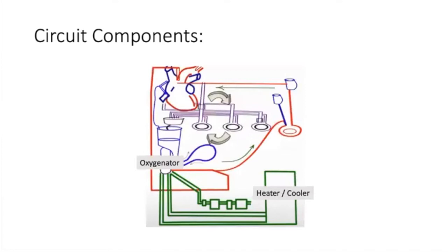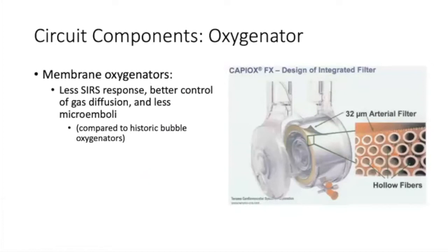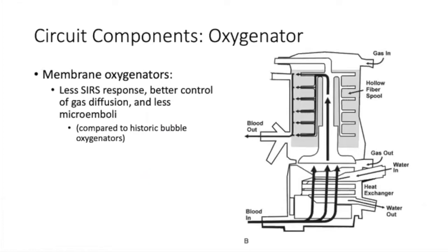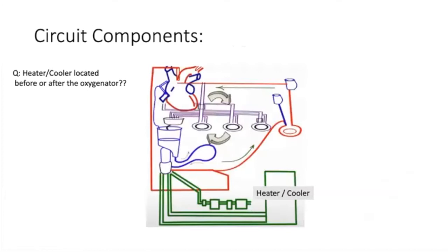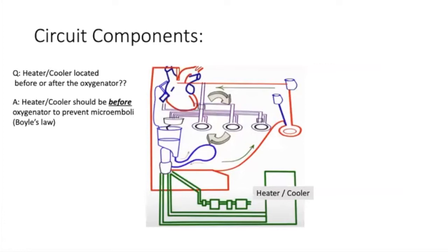Membrane oxygenators are essentially the only oxygenators in use today. They offer much less SIRS response, better diffusion control of gases, and less microemboli compared to historic bubble oxygenators. The heater-cooler uses a heated coil with a water bath to adjust blood temperature as it flows through. A common source of confusion is whether the heater-cooler should be before or after the oxygenator — it should be before, to prevent microemboli and outgassing: if blood already has a diffused oxygen component and is then heated, it can form microemboli, whereas heating before oxygenation avoids this.